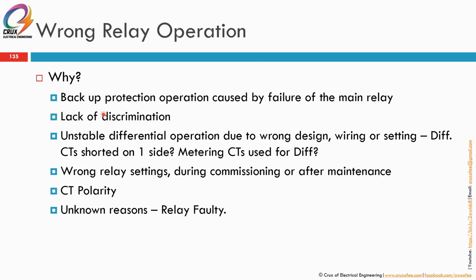Second issue is lack of discrimination. By right, you should discriminate between 250 to 400 milliseconds, depending on the type of relay. If you set it too close, lack of discrimination, or maybe you did not set it at the maximum fault current, this can cause mal-operation of your relay. Maybe more than one relay can trip at the same time. Then there is unstable differential operation due to wrong design, wiring or setting, CT shorted on one side, metering CT used. This one is more related to differential relay.